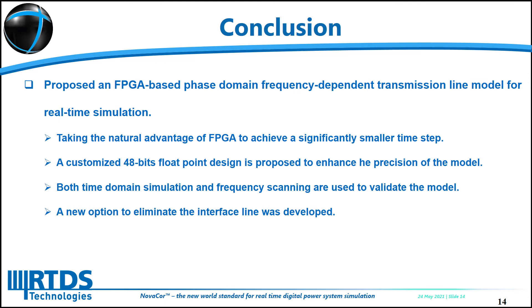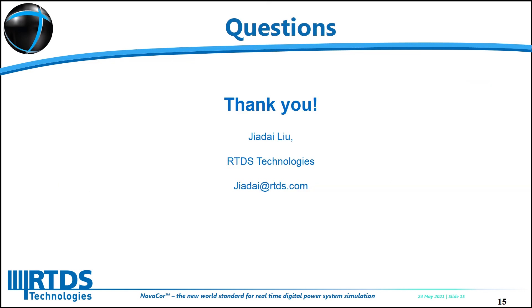In conclusion, we have proposed a FPGA-based phase-domain frequency-dependent transmission line model for real-time simulation. Taking advantage of FPGA's parallel nature, the FPGA-based model achieves a significantly smaller timestep. We proposed a customized 48-bit floating-point design to enhance the precision of the model, and have used both time-domain simulation and frequency scanning to validate it. We have also developed a new option to eliminate the interface line, which brings more accurate frequency response at the price of increasing the timestep from 3 microseconds to 5 microseconds. Thank you to everyone who joined, and I'd be glad to take any questions.